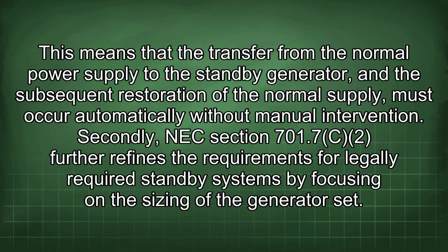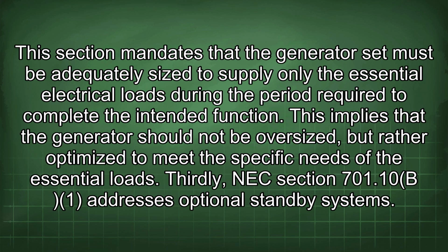Secondly, NEC Section 701.7 further refines the requirements for legally required standby systems by focusing on the sizing of the generator set. This section mandates that the generator set must be adequately sized to supply only the essential electrical loads during the period required to complete the intended function. This implies that the generator should not be oversized, but rather optimized to meet the specific needs of the essential loads.